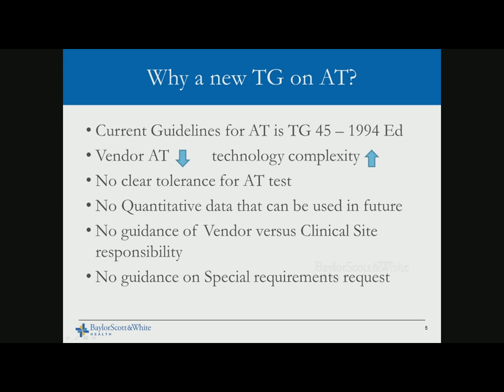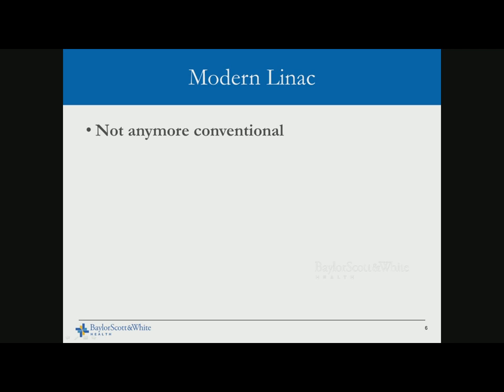There is also a need for guidance on what is the vendor's responsibility versus the clinical site's responsibility. There have been anecdotal cases where disagreement between facility and vendor caused acceptance testing to stall due to lack of understanding. There is also a need for guidance on special requirements like beam matching for multiple machines, non-conventional energies, and fine-tuning radiation isocenter — these need to be clearly stated in the contract.